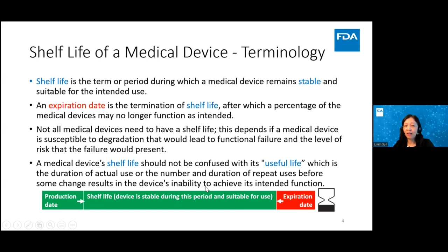Also, a medical device's shelf life should not be confused with its useful life, which is the duration of actual use or the number and the duration of repeat uses before some change results in the device's inability to achieve its intended function. The United States Pharmacopoeia defines stability as the extent to which a product retains, within specific limits and throughout its period of storage and use, the same properties and characteristics that it possessed at the time of manufacture.